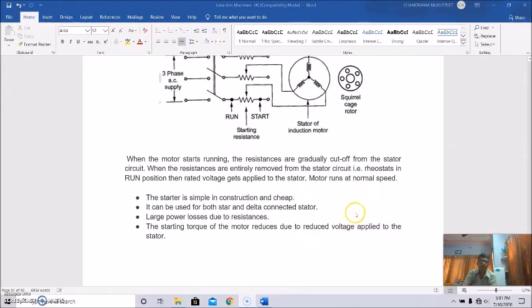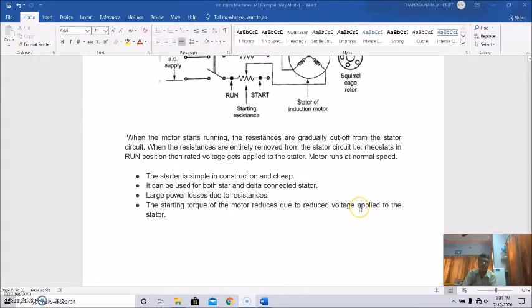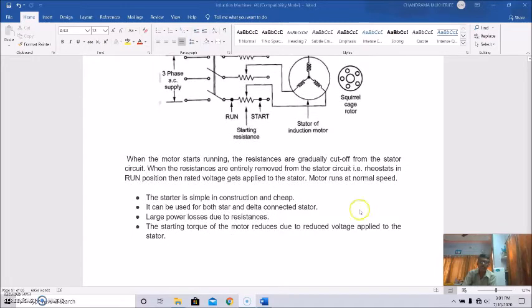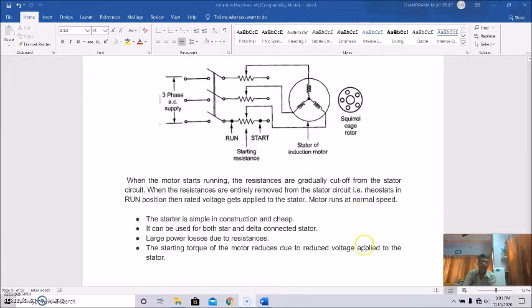Okay, so the starter is very simple in construction and it is cheap. It can be used for both star and delta connected stator, and large power losses due to this resistance will definitely happen. And the starting torque of the motor reduces due to the reduced voltage applied to the stator at starting.